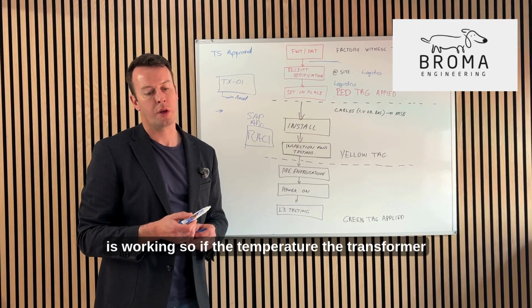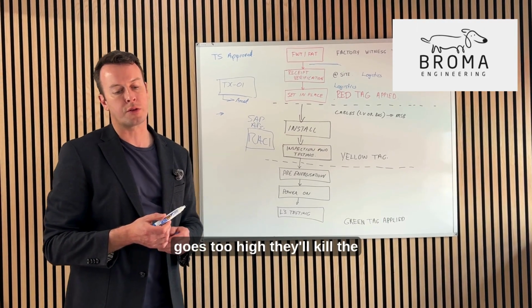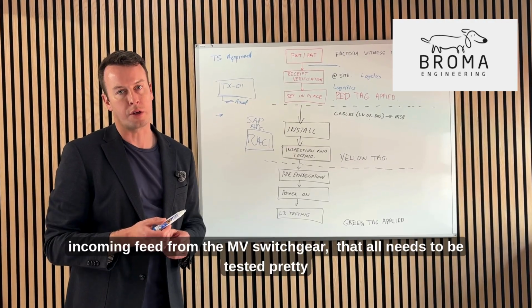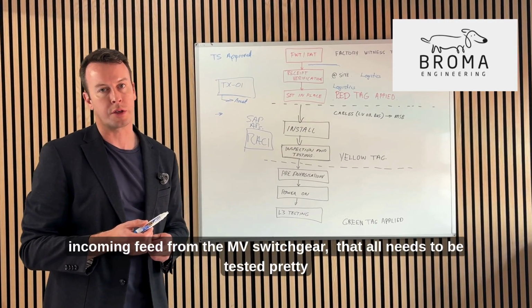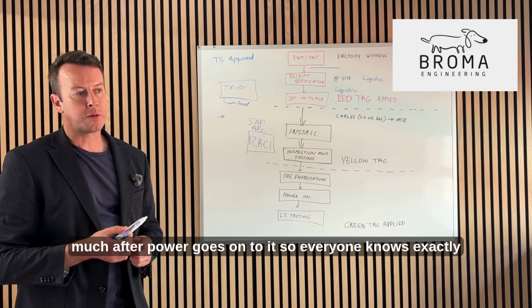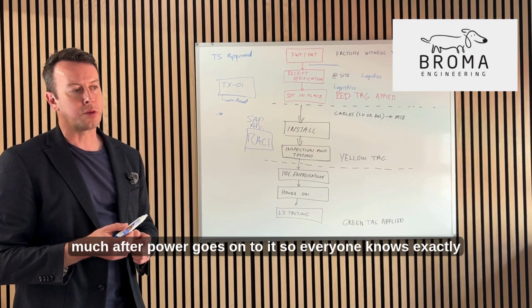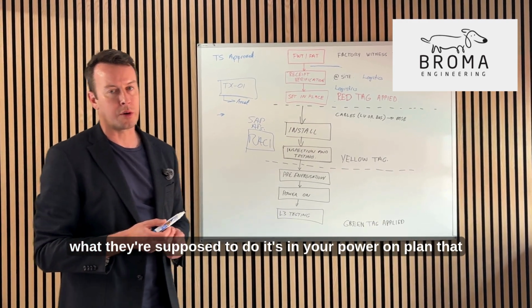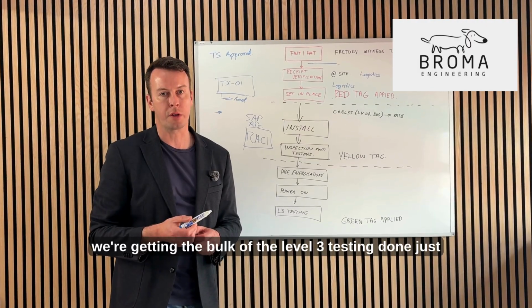Switch is working, so if the temperature of the transformer goes too high, that'll kill the incoming feed from the MV switchgear. That all needs to be tested pretty much after power goes onto it, so everyone knows exactly what they're supposed to do. It's in your power-on plan that we're getting the bulk of the level 3 testing done just after.